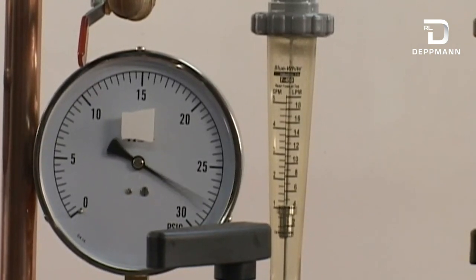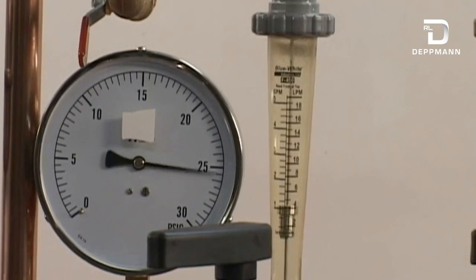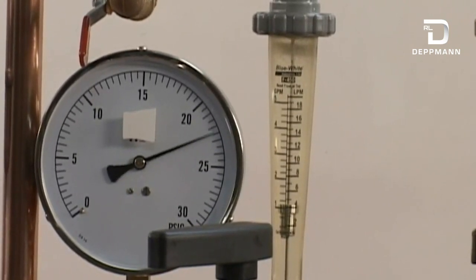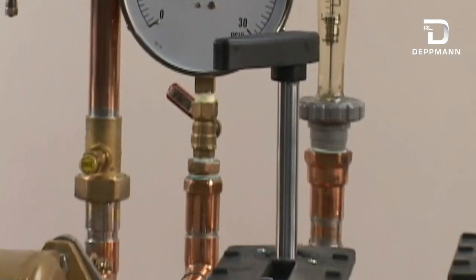Now I'm going to ramp this back down. And as you notice, as I ramp it down, it still stays at 1 GPM. This cartridge in this pressure independent valve is maintaining and holding that 1 GPM.